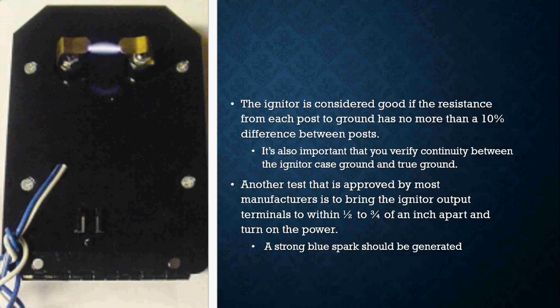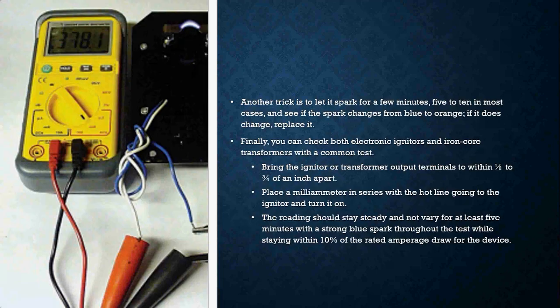Another test that is approved by most manufacturers is to bring the igniter output terminals to within a half to maybe 3/4 of an inch apart and then turn the power on. When you turn the power on, you should get a nice strong blue spark generated across those terminals. Another trick is to let the spark run for a few minutes, by about 5 to maybe 10 minutes in most cases, and see if the spark changes from a blue to an orange color. If it does, replace it.